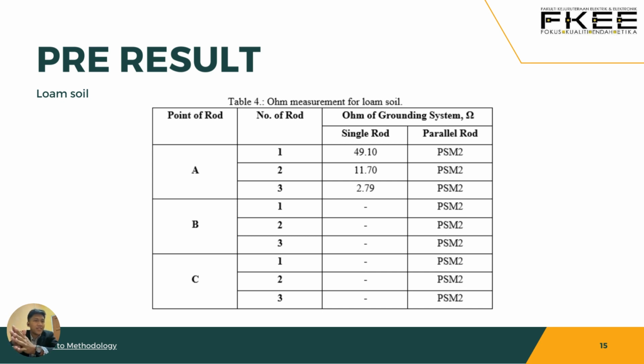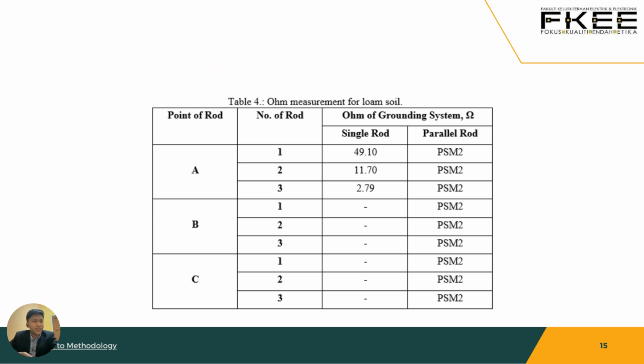As you can see, for the single rod at the loam soil system, the first rod I buried gave 49.1 ohm. Adding one more rod, making it 2 rods in the soil, the result changed to 11.7 ohm. Adding another rod for a total of 3 rods, the grounding system at that soil type using single rod grounding gave a value of 2.79 ohm, which meets the requirement. That's the pre-result I can show.